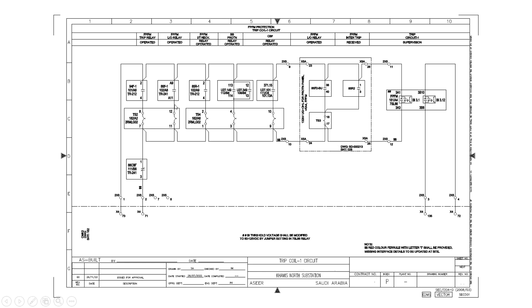In the simple scheme, when a 94 self-reset relay is operated, it gives a tripping signal to the trip coil of the circuit breaker. After the fault disappears, the 94 gets self-reset and the positive disappears from that part.